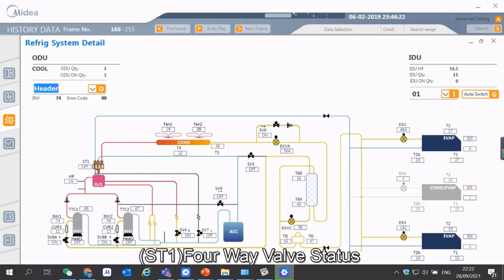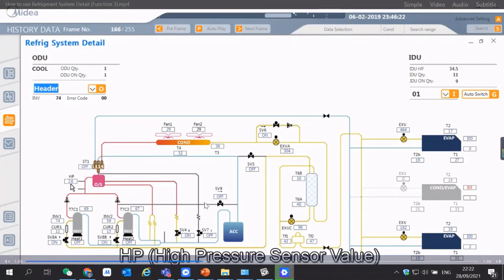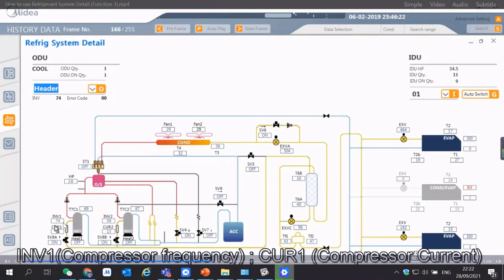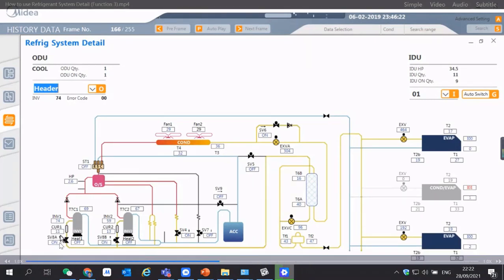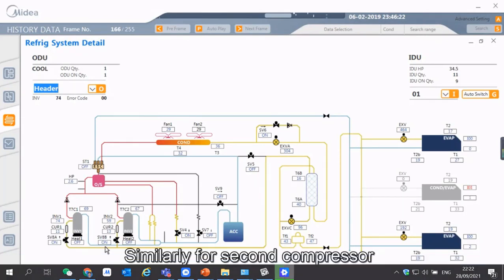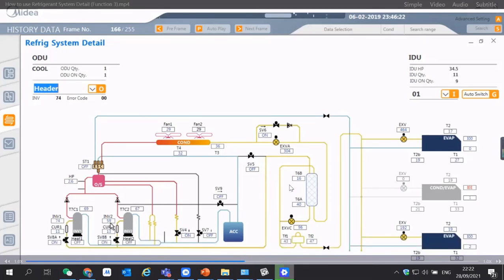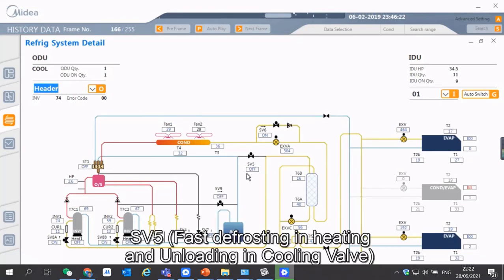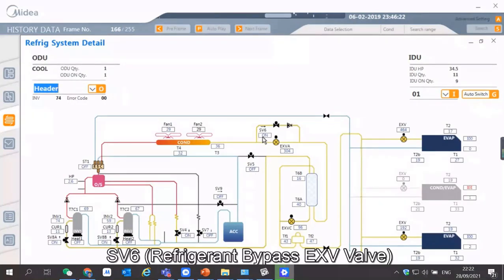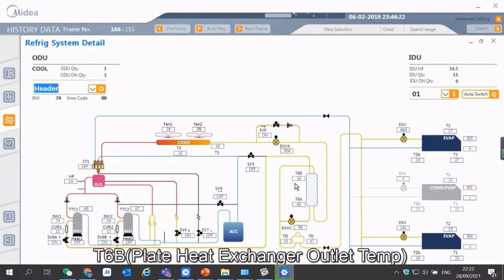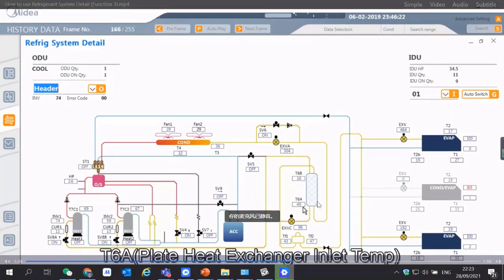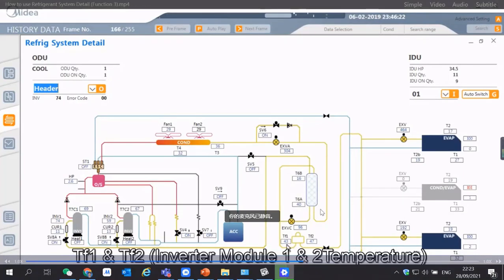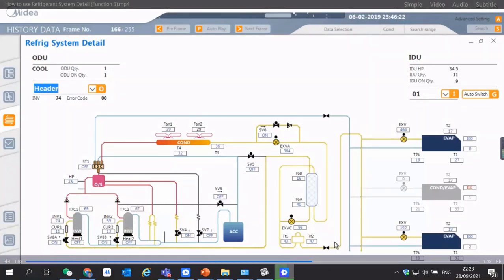So the four-way valve status on or off, the high pressure sensor value, and the discharge temperature of compressor 1 and compressor 2, inverter compressor frequency, and compressor current. Then this SV8A, the compressor vapor injection valve, and the crankcase heater are turned on or off, and similarly for the second compressor. And all these valve values, this plate type heat exchanger and this return valve, right? So we can check the status of the different valves from here. This is the refrigerant bypass valve and the EXV of the ODU, and this is the plate heat exchanger opening degree, sorry, the sensor values. In this way we can check very detailed parameters for the outdoor unit as well.